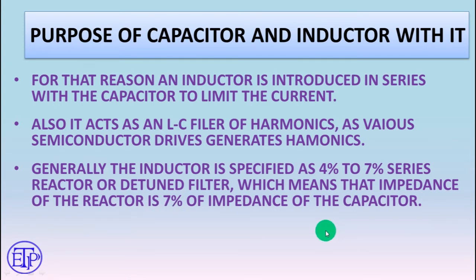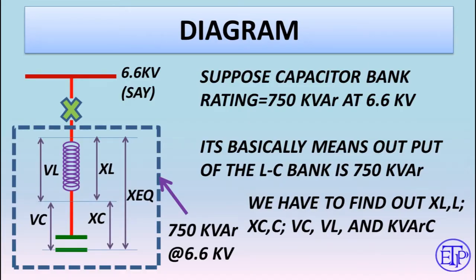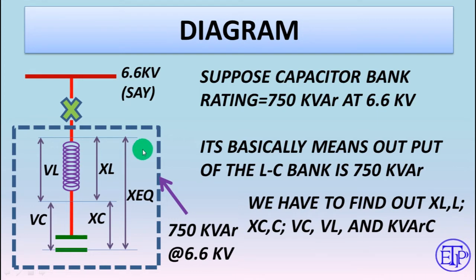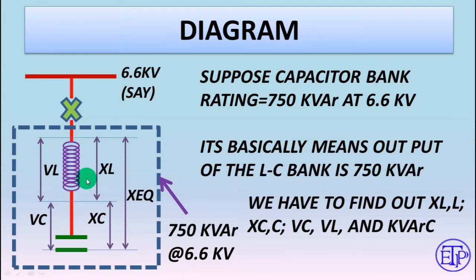In this video, we will further see how those values are calculated. In the diagram, suppose this is the 6.6 kV bus and this is the capacitor — an inductor is connected in series with the capacitor. Suppose you have 750 KVAR at 6.6 kV. The entire capacitor-inductor setup will give you 750 KVAR and the voltage across the terminals will be 6.6 kV. We need to find the voltage across the capacitor — whether it is 6.6 kV or higher or lower — accounting for the voltage drop due to the inductor.